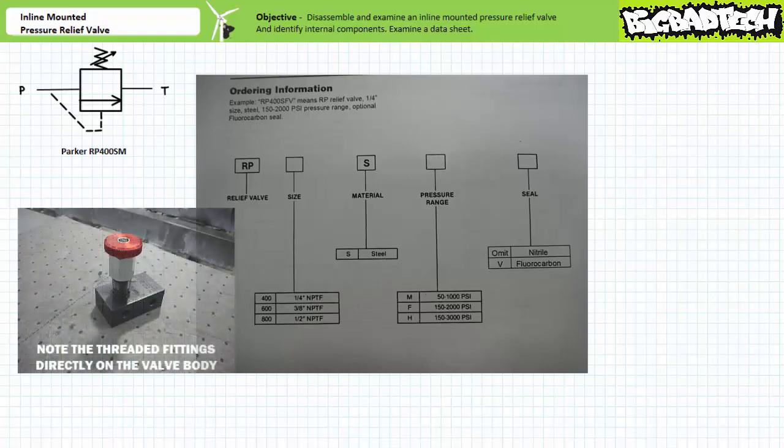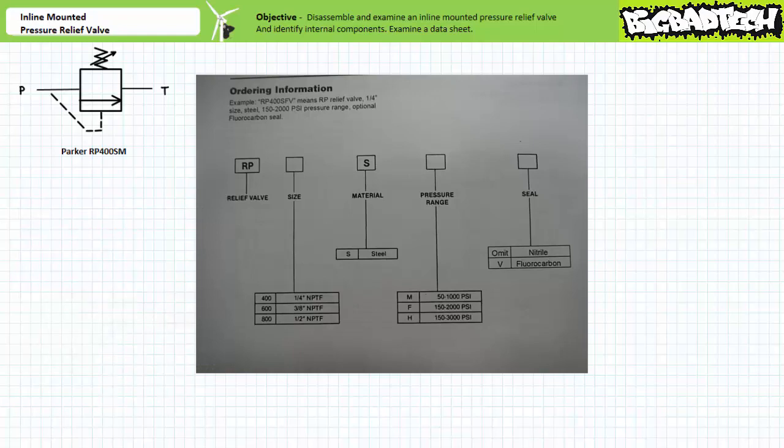This particular valve is inline mounted because fluid conductors are intended to be directly attached to it. S indicates the valve body is made out of steel. The M pressure range indicates the valve is intended to regulate pressure between 50 to 1000 psi. Since the fifth identification field is omitted, we know this valve has nitrile seals.